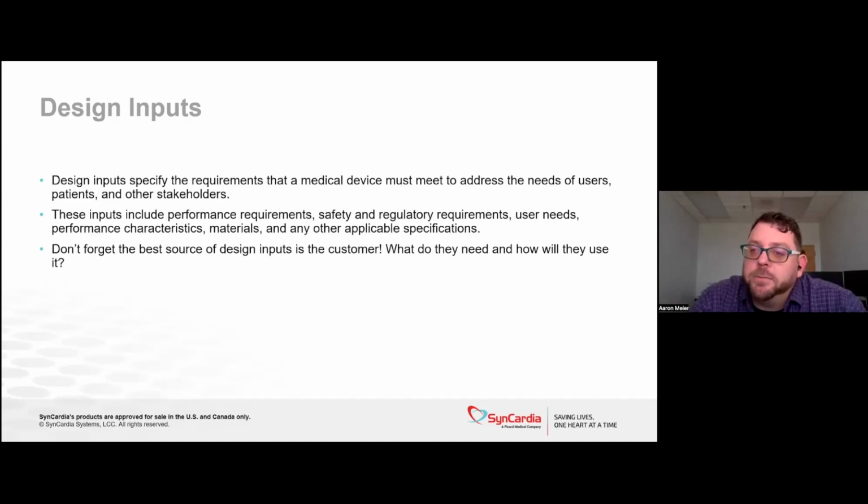Talk to your customers. Usability, particularly in an implantable medical device, such as a total artificial heart, is very important. What are those risks of your customer using your device? So those really go into your design inputs. What do I need to build?